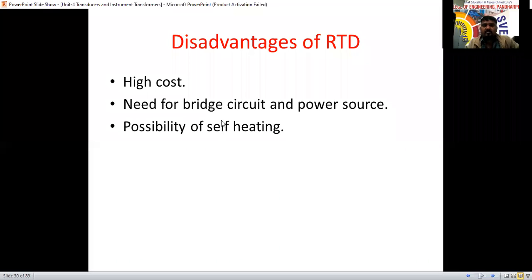So there is the need for the bridge circuit and power source. There is a possibility of self-heating. Because it is connected to the external supply, self-heating will develop in that material for the load and all. For that reason, the value will change over there. That is the disadvantage of RTD.